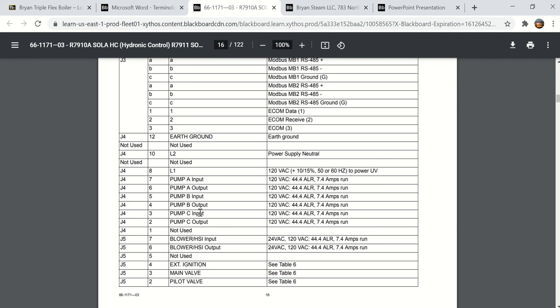Here's the bad thing. If you ruin one of these contacts because you put too much current through it or something shorted out, you're not going to replace that. You're not going to repair it. You're going to have to replace the whole controller. So it's probably better to consider these as light duty or pilot duty, and don't try to run higher amperage equipment through them.